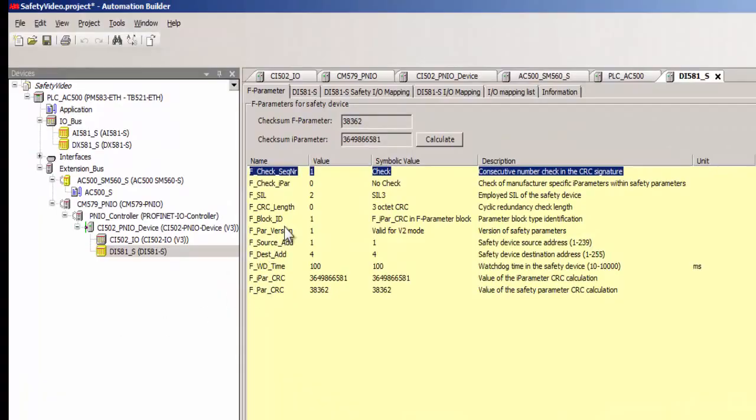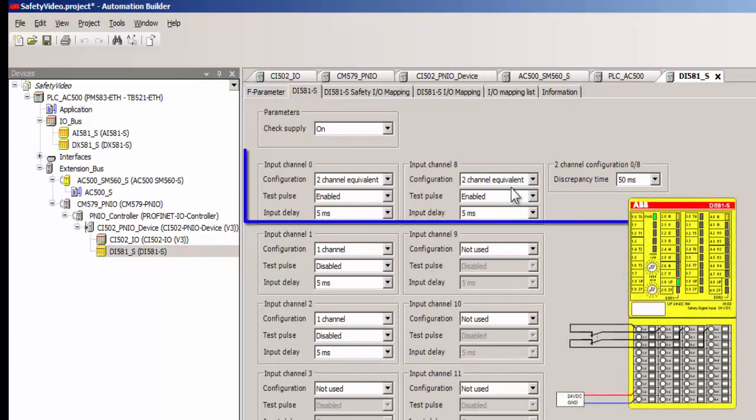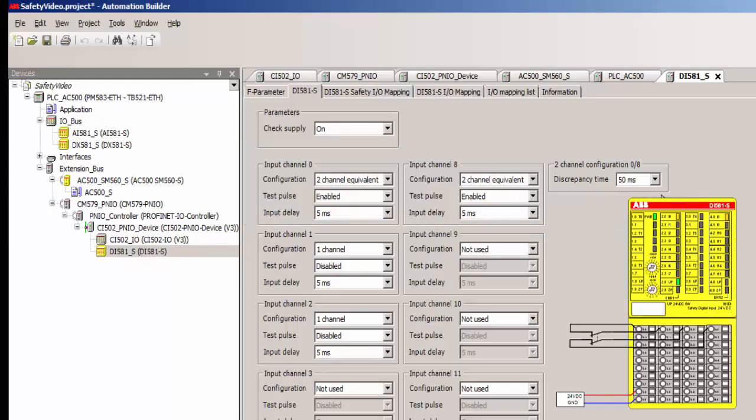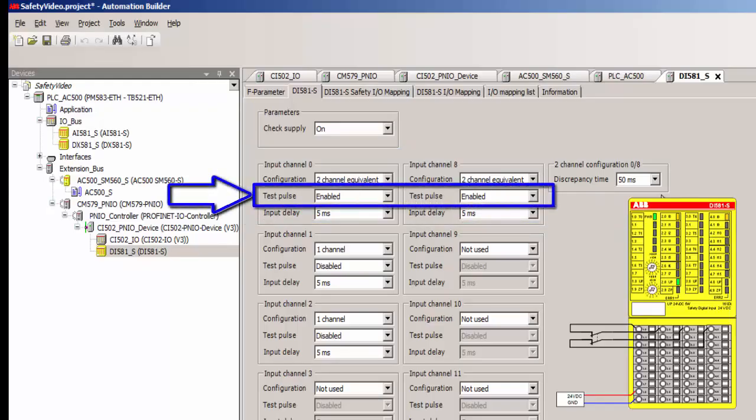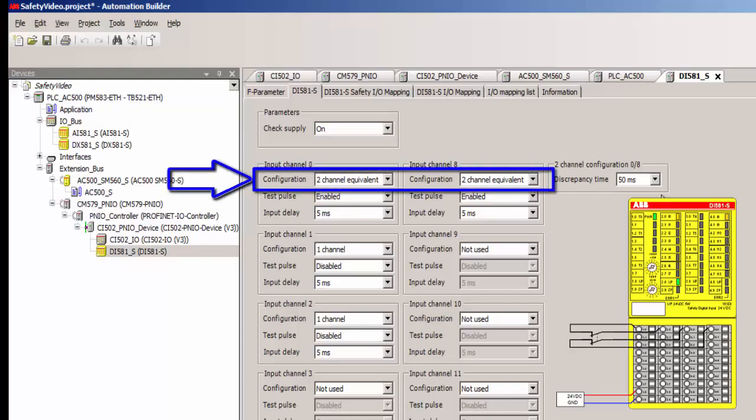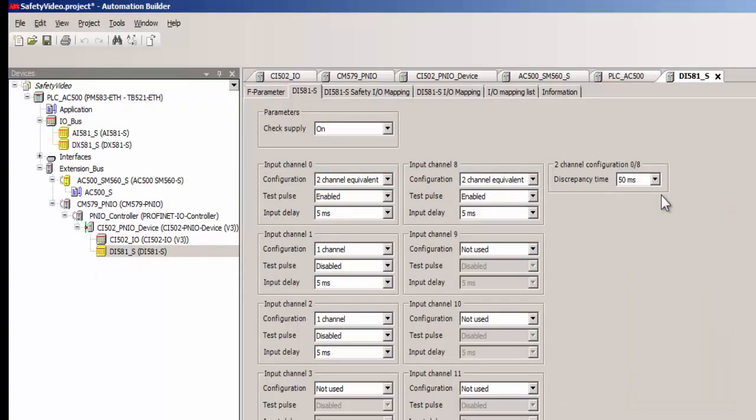In order to reach SIL 3, the emergency stop button is wired as a two-channel input to the safety digital input module. Also one has to use a SIL 3 rated normally closed push button, preferably with a test pulse enabled. This means the safety push button is powered from the safety module itself. In this particular case, these two channels are configured as equivalent type and powered by two separate test pulses in order to enhance the diagnostic coverage factor.